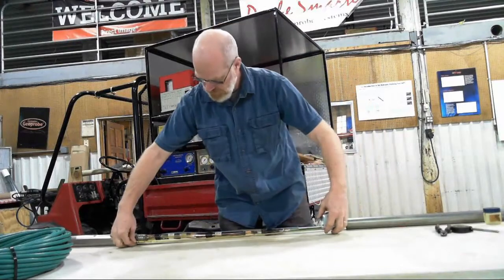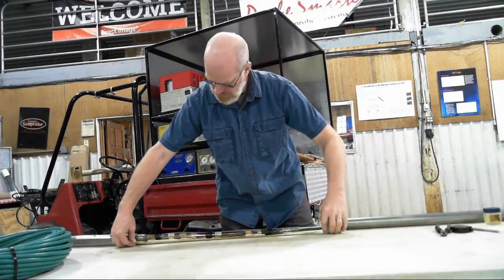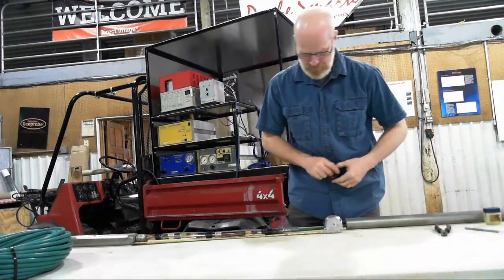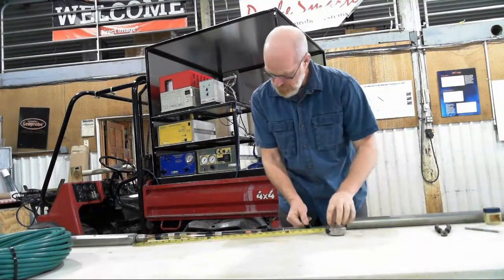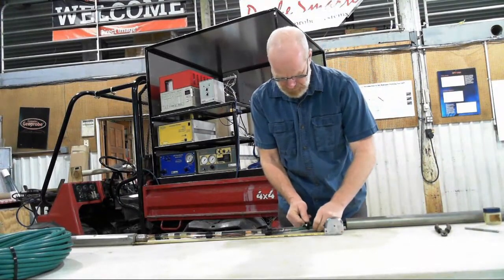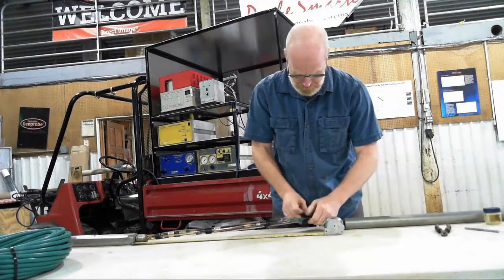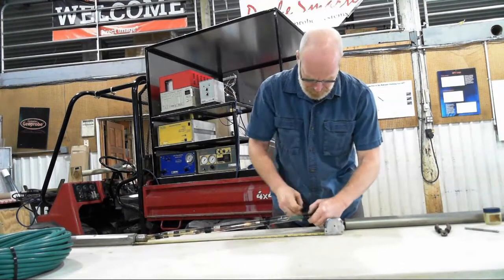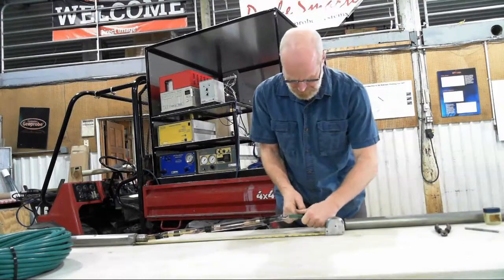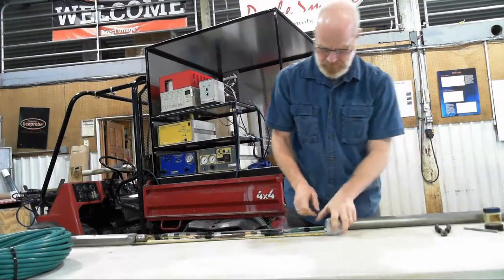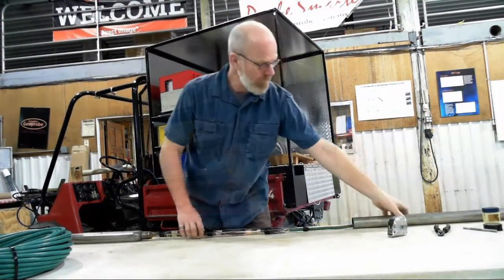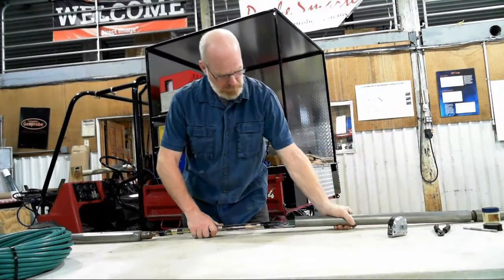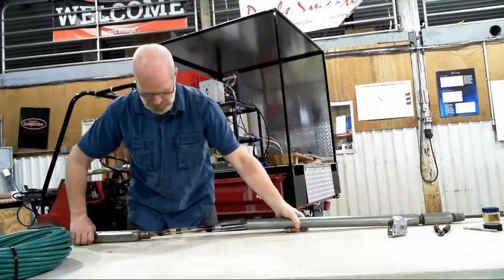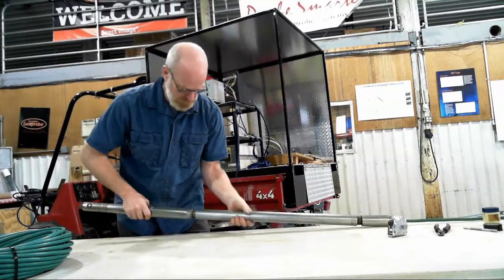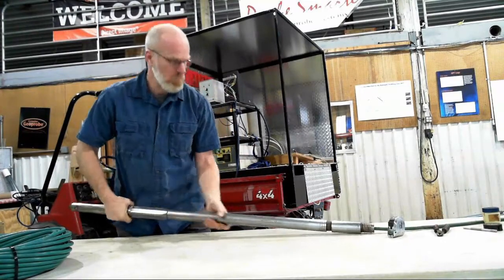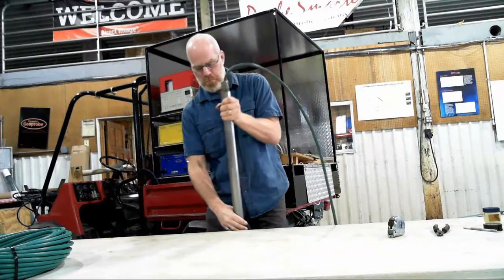Next, I will measure 27.5 inches from the shoulder of the probe at the base of the threads and will wrap the trunk line with 8 to 10 wraps of electrical tape. This will serve as a strain relief for the water seal to press against. Finally, we'll be able to slide the connection tube over the wire connections. It should slide over this section very easily and not get stuck. If it does, you'll need to redo the connections to make them smaller. Make sure all the rotation is done with the connection tube.